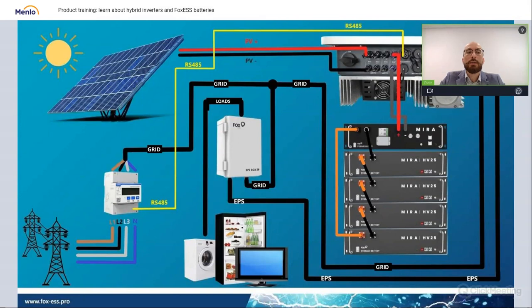EPS box is an automated transfer switch. If there is a blackout and there is no energy in the grid, this inverter will start to output energy on the emergency power output, this energy to the local grid.